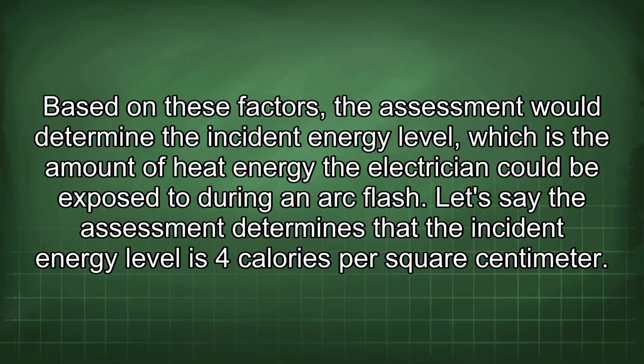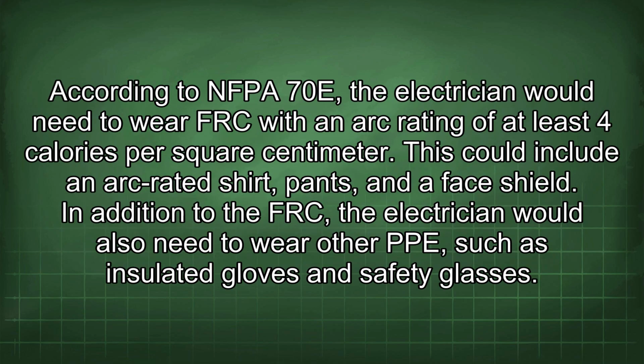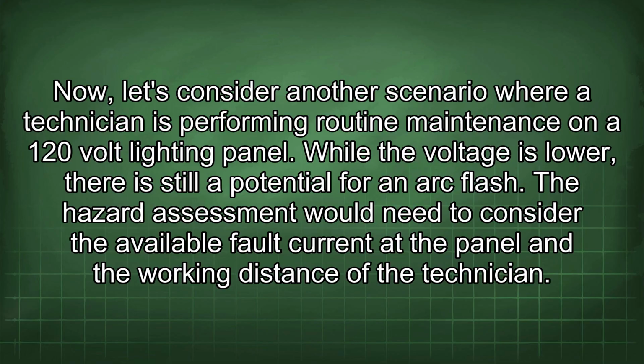Let's say the assessment determines that the incident energy level is 4 calories per square centimeter. According to NFPA 70E, the electrician would need to wear FRC with an arc rating of at least 4 calories per square centimeter. This could include an arc-rated shirt, pants, and a face shield. In addition to the FRC, the electrician would also need to wear other PPE such as insulated gloves and safety glasses. Now, let's consider another scenario where a technician is performing routine maintenance on a 120-volt lighting panel.